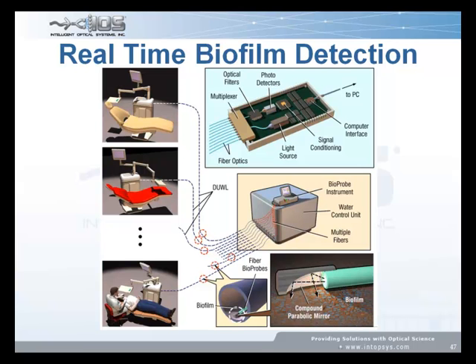They're supposed to clean out those dental lines, and they do. They sluice them out usually with a chlorine solution. But there is an opportunity for biofilms to grow in there, and if the wrong stuff is growing in there, you can wind up, if it sits in the lines overnight and you're the first patient in the morning, with some serious levels of toxins in that little Dixie cup. So the idea was to make a probe that you can use to snake down those water lines and just tell, as I pull it back, is there biofilm there, and if there is, is it active or not?